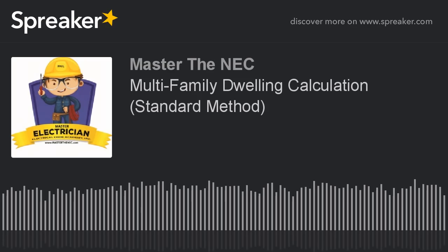Step 2 kind of covered appliances and laundry, and the square footage, you added them all together. Now comes step 3. Now I am allowed to apply what's called a demand factor. You'll also notice that it states that at the end of 220.52(A) and (B), in the last paragraph, it says shall be subject to the demand factors provided in Table 220.42.